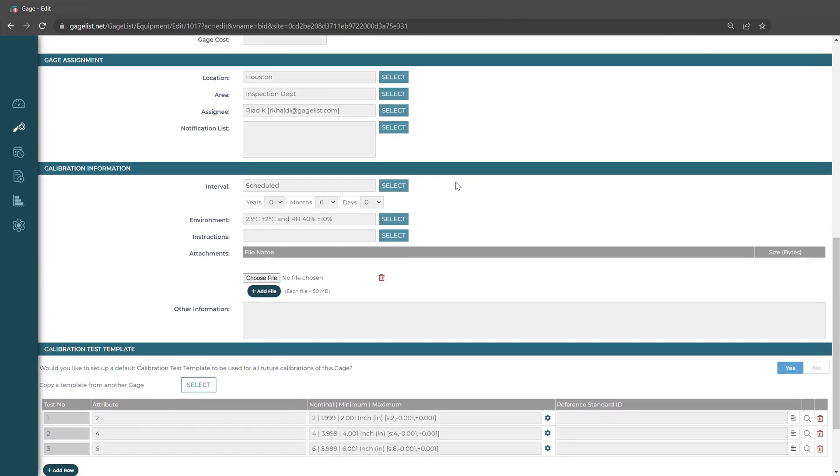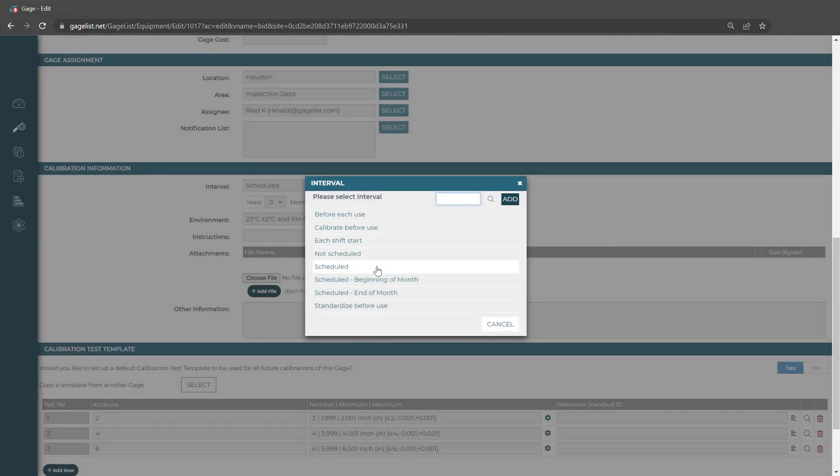The first thing we want to do is make sure that we have our scheduling set up. We can choose the interval. I have it set to scheduled, and I have the time set to six months. We can make this whatever time frame that we'd like. We could also choose something like beginning or end of month if we calibrate at the beginning or the end of the month.